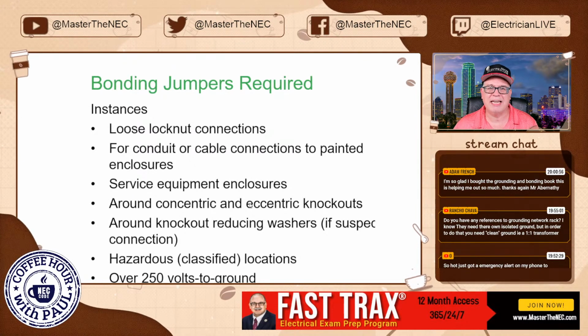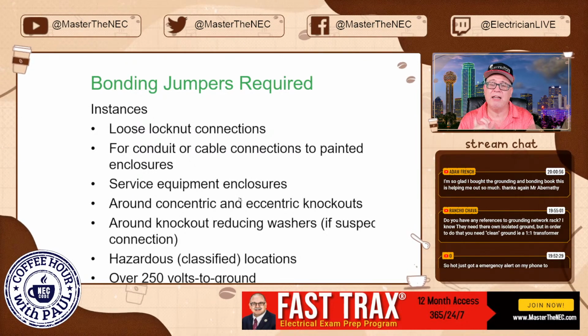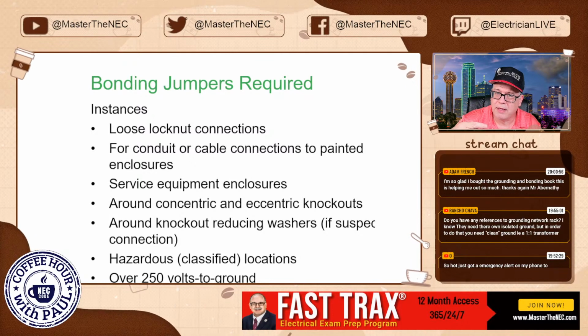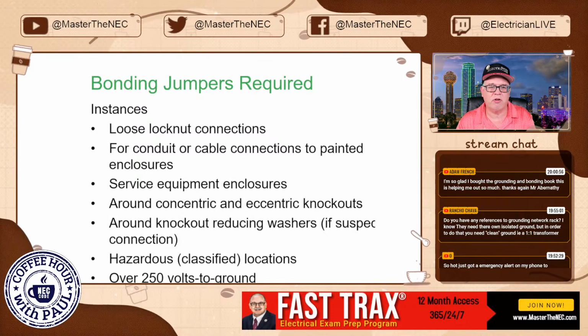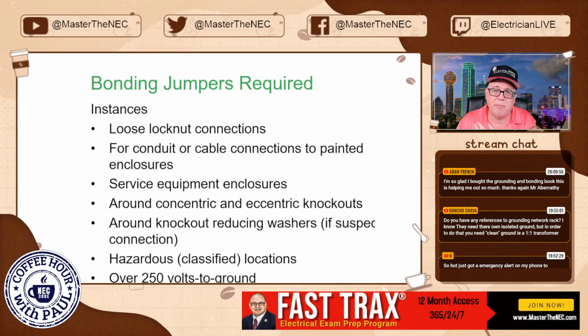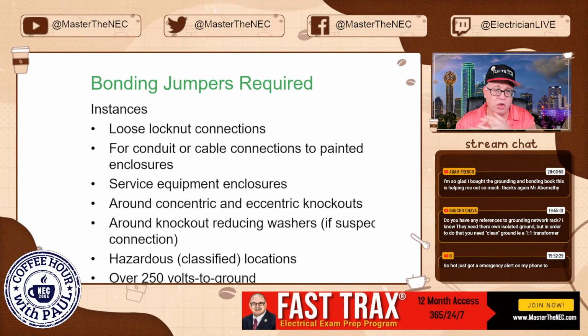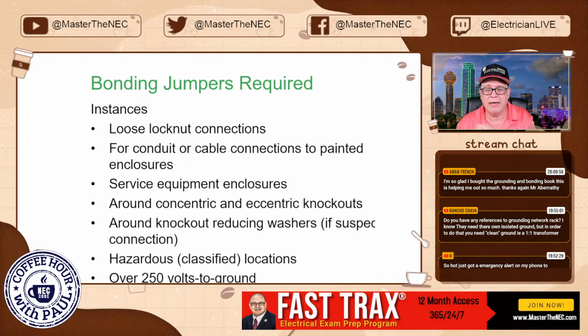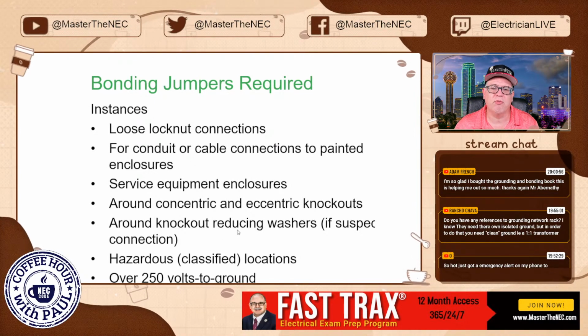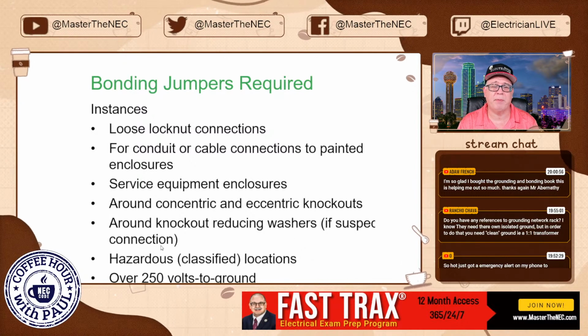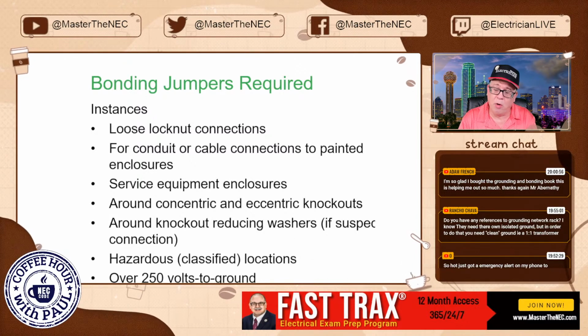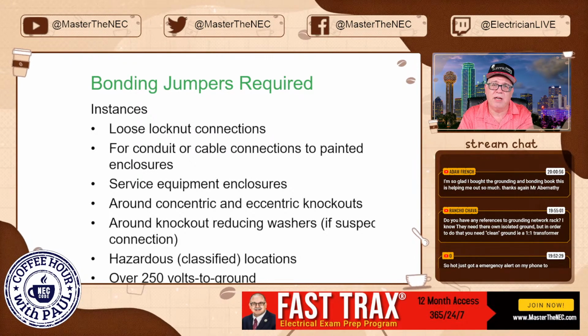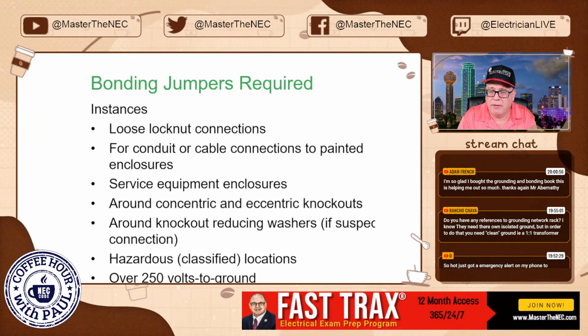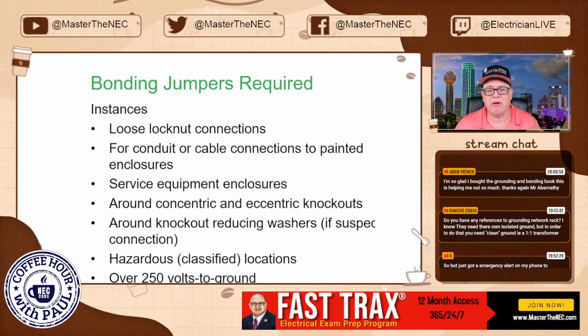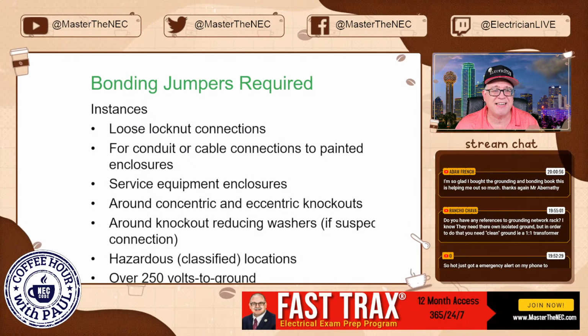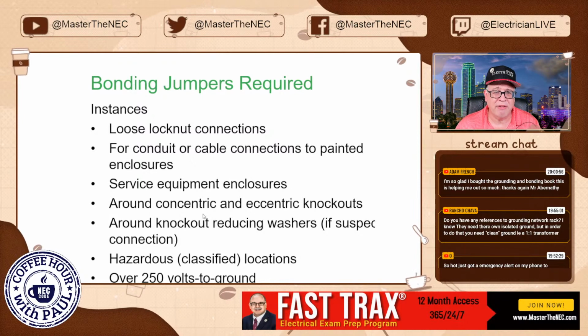Service equipment enclosures, again, bonding jumpers if you are running it, because you have a little more assurance than normal. Okay, so if you have any concentric or eccentric knockouts or anything that looks impaired and it's got service conductors coming in, then you are going to need a bonding jumper. Around KO reducing washers, if you don't believe that reducing washer is going to be an adequate connection, then again, bonding jumpers may be necessary around that. If that connection is suspect, somebody beat to death that reducing washer.